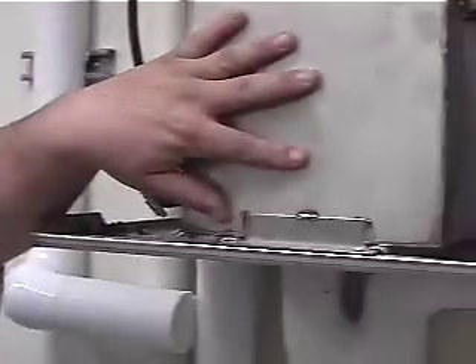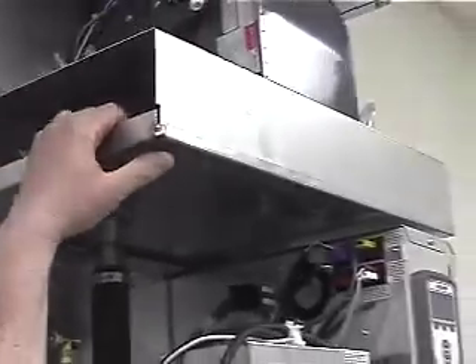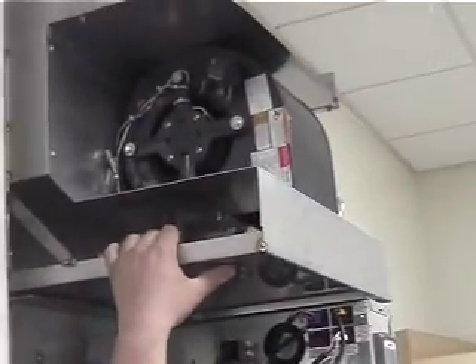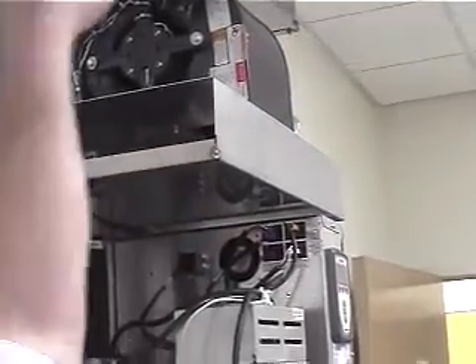So basically we have a pot here that boils our water. Once it boils, it comes up. There's a dispersion tube up here, a tube with a T with little teeny orifices in it. Blows the humidity out underneath this pan. This fan then is going to blow air out underneath here so it absorbs that humidity immediately because it's steam. And then it comes back out and around the air, back out and shoots it above.